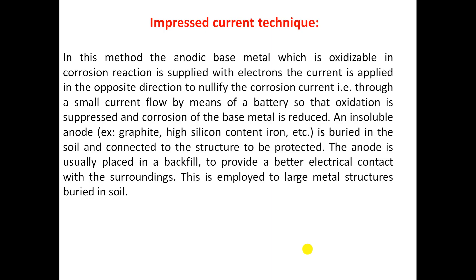The next method in cathodic protection is the impressed current technique. In this method, the base metal — which is oxidizable and prone to the corrosion reaction — is supplied with electrons. A current is applied in the opposite direction to nullify the corrosion current, through a small battery. This suppresses oxidation and reduces corrosion of the base metal. An insoluble anode is placed in the soil and connected to the structure to be protected. The anode is usually placed in a backfill to provide better electrical contact with the surrounding medium. This method is employed for larger metal structures buried in soil.